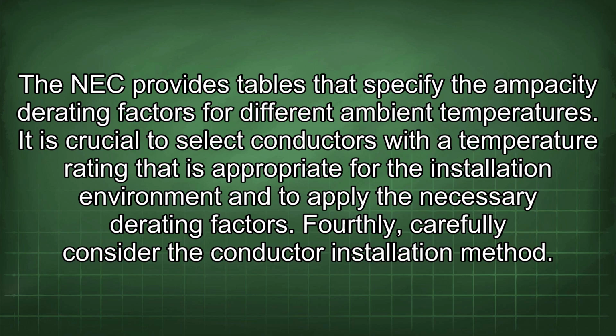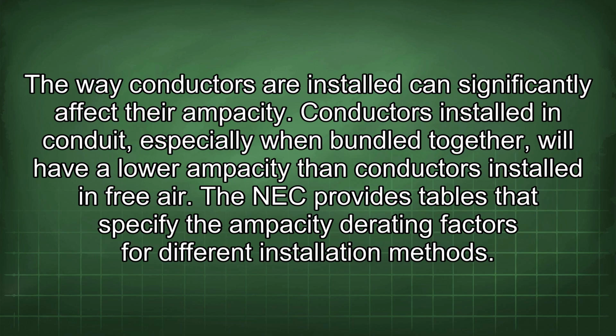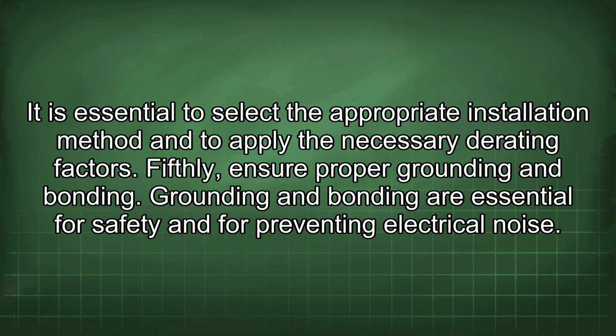the necessary derating factors. Fourthly, carefully consider the conductor installation method. The way conductors are installed can significantly affect their ampacity. Conductors installed in conduit, especially when bundled together, will have a lower ampacity than conductors installed in free air. The NEC provides tables that specify the ampacity derating factors for different installation methods. It is essential to select the appropriate installation method and to apply the necessary derating factors.